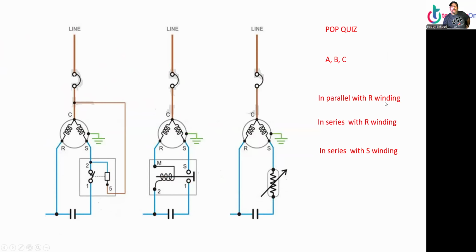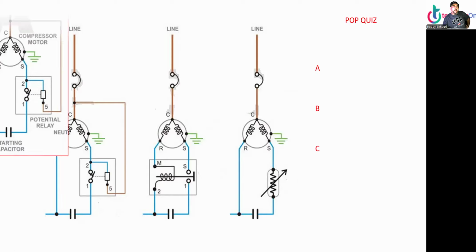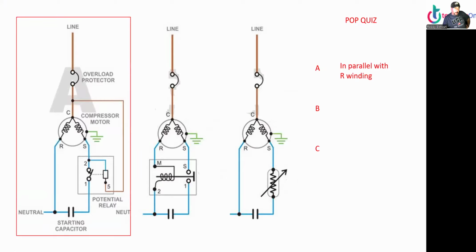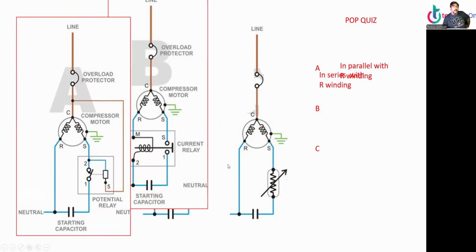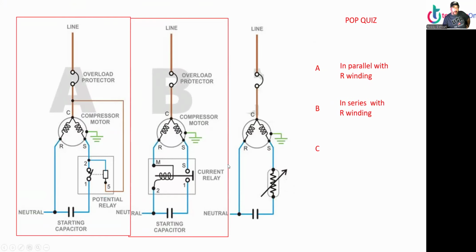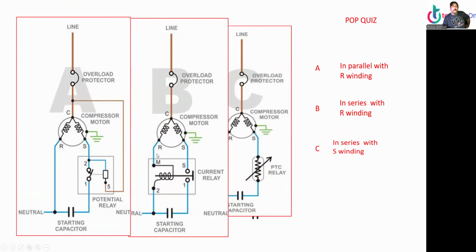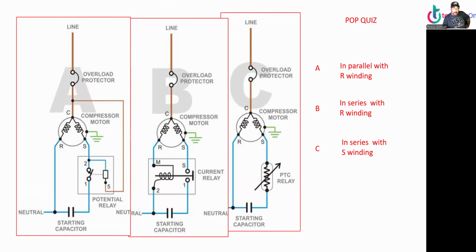All right, now, pop quiz. What is in parallel with the run winding, in series with the run winding, or in series with the start winding? It's pretty simple, right? A, B, C. So A, right? The potential relay is in parallel with the run winding. You can see the run winding is here and it's parallel with it, side by side. While the current relay is in series with the run winding. And the PTCR is in series with the start winding because it takes the start winding out of the system. They all do the same thing, just in different ways.